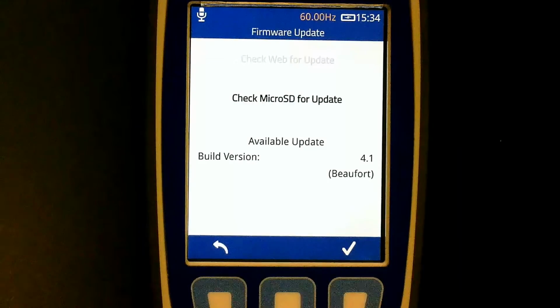And how does one get the latest update? Just call or email us with your serial and hardware version numbers from the About screen. The UltraTEV Plus 2 is purposefully designed with minimal settings to avoid compatibility problems between surveys in the future. However, a full factory reset is possible.